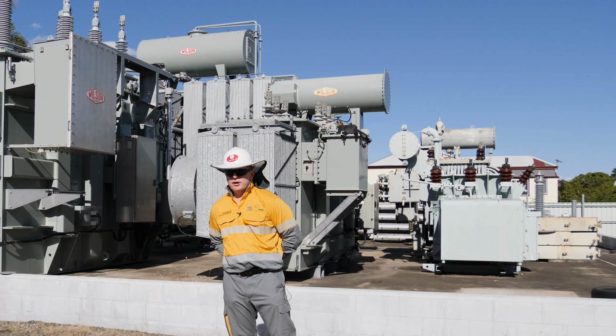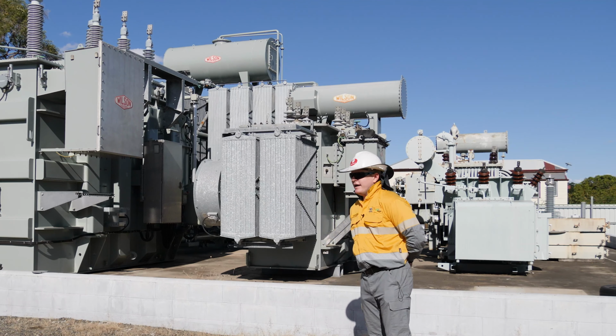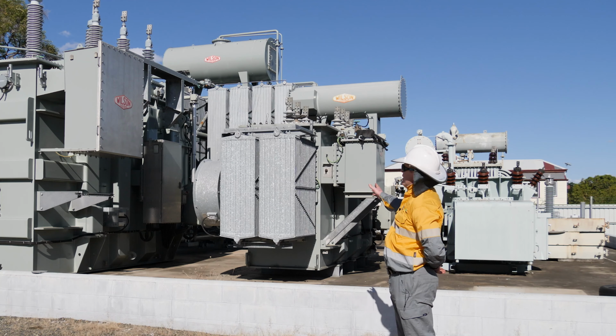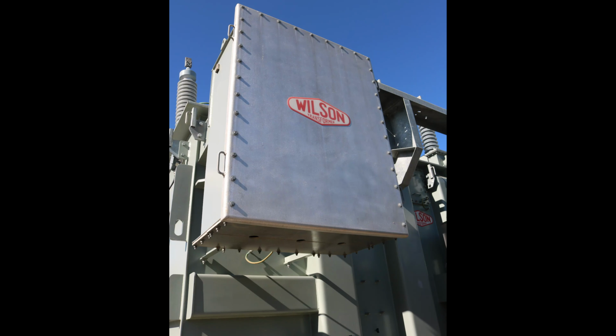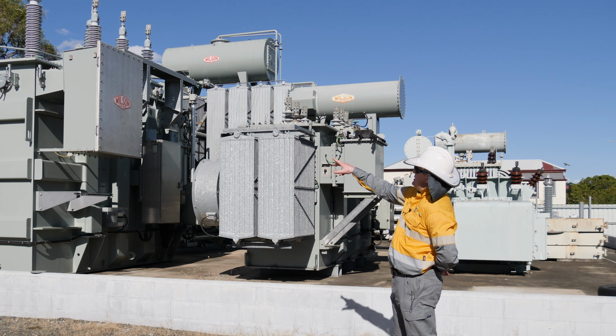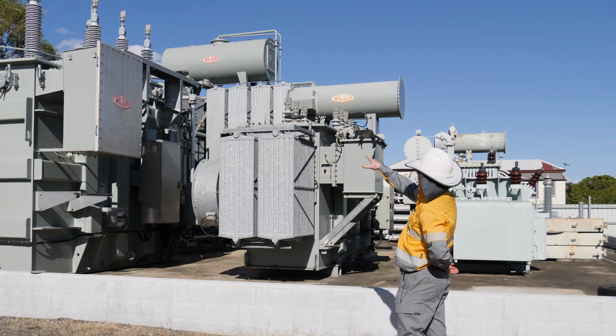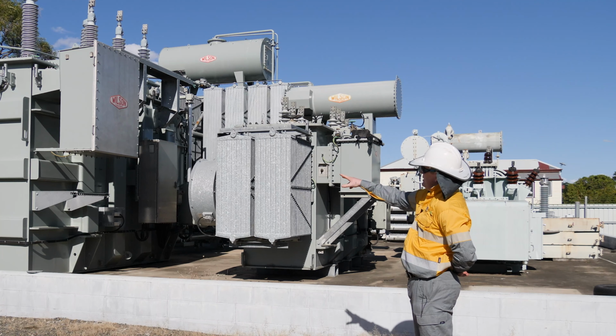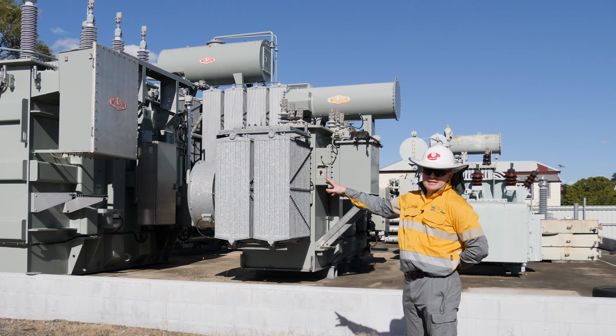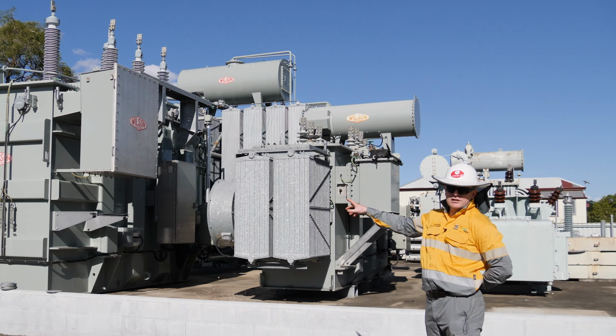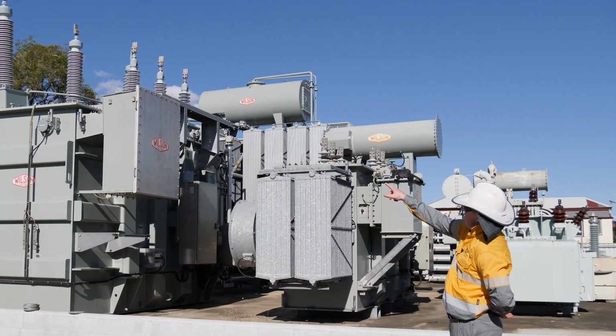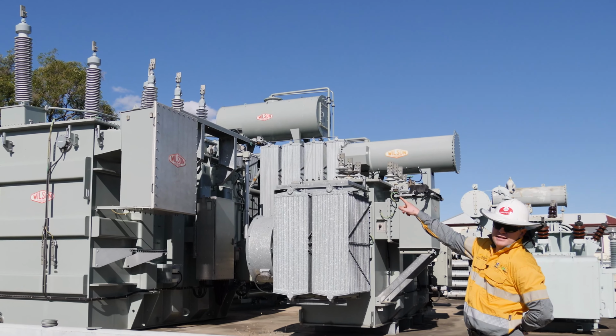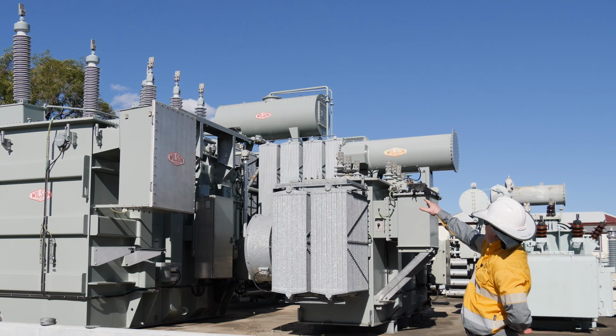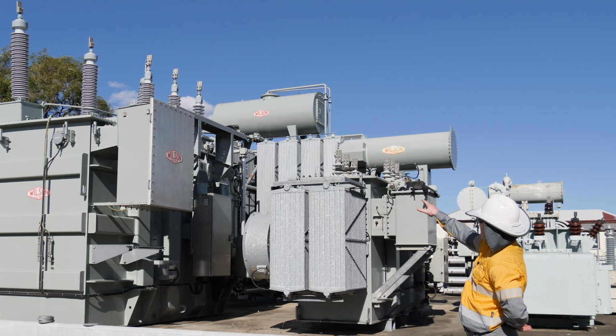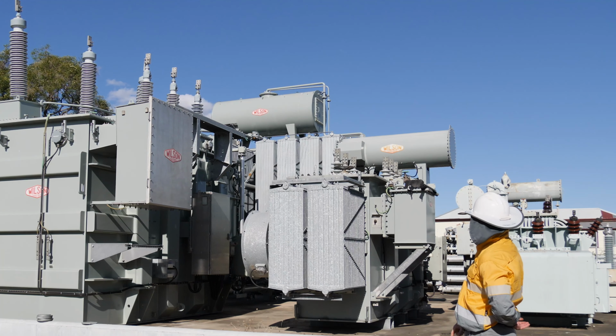Behind me, we've got a couple of transformers that we can talk a bit about. We've got a big one and a little one. On the larger transformer, which is a Wilson transformer, you can see that there are two sets of bushings. There's a large set on the left and a smaller set on the right. This transformer is a 132 kV to 66 kV transformer, and it's rated at 100 MVA. The larger bushings are for the 132 kV incomers, and the smaller bushings are for the 66 kV outgoers that are carrying the transformed voltage.